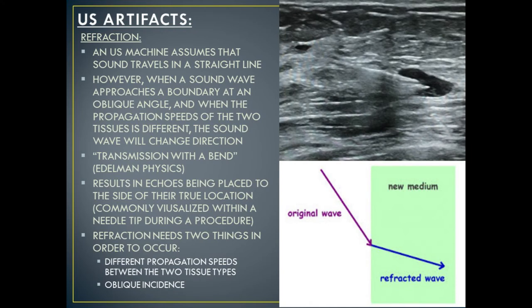Our next type of velocity error artifact is known as refraction. Refraction occurs because an ultrasound machine assumes that sound travels in a straight line. However, when a sound wave approaches a boundary at an oblique angle and when the propagation speeds of the two tissues are different, the sound wave will change direction — known as refraction, or transmission with a bend. This results in echoes being placed to the side of their true location, commonly visualized within a needle tip during a procedure, where the needle tip looks like it is bent. Refraction requires two things: different propagation speeds between the two tissue types, and oblique incidence.